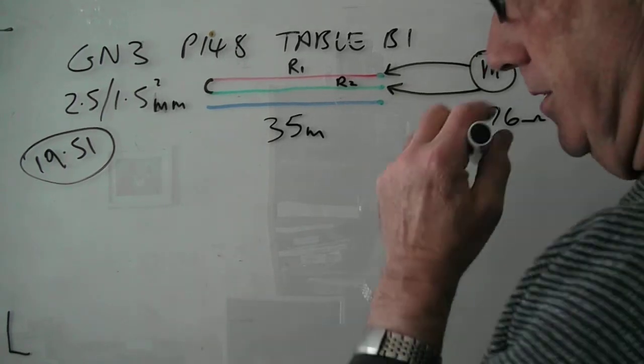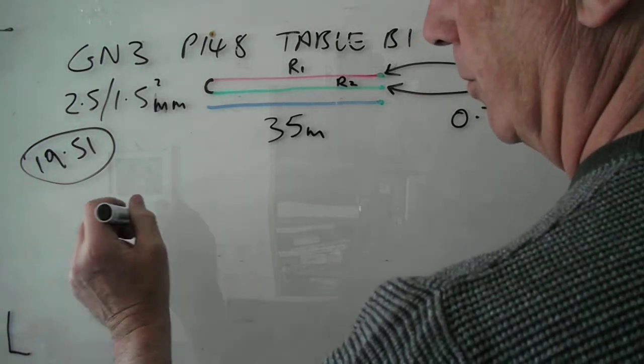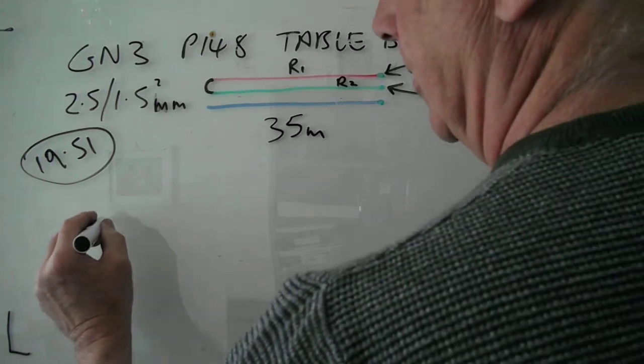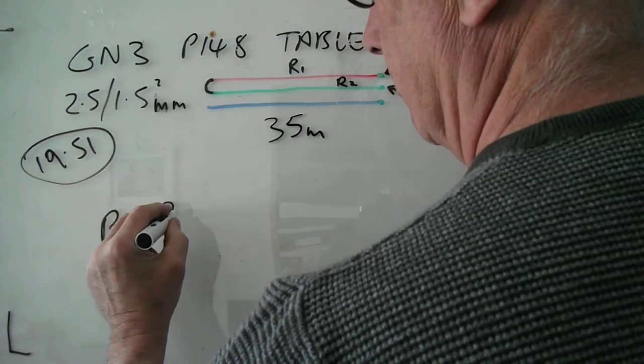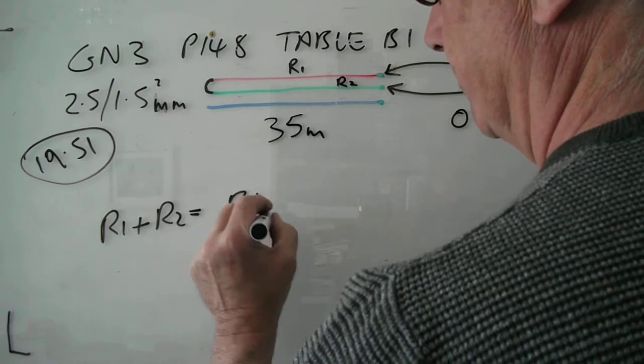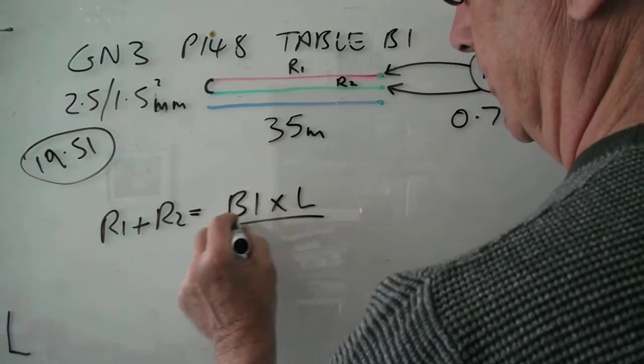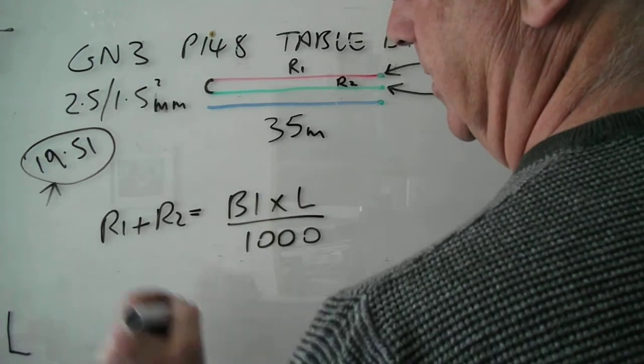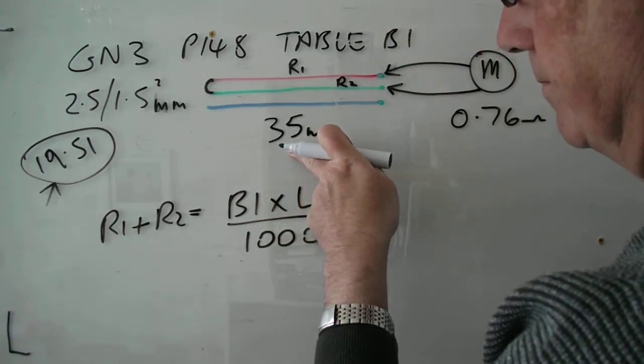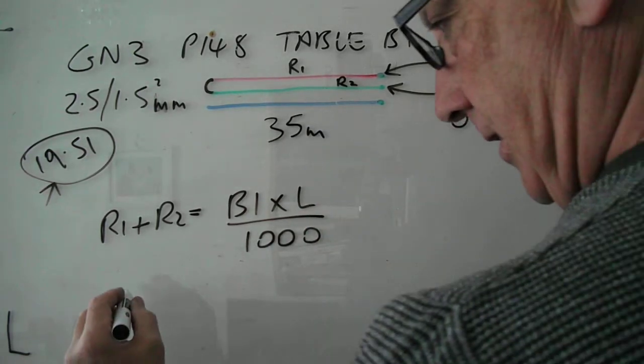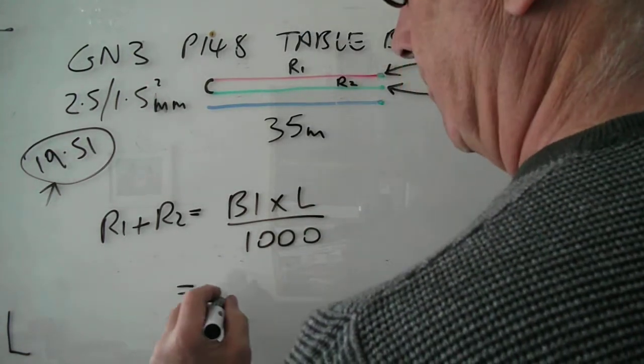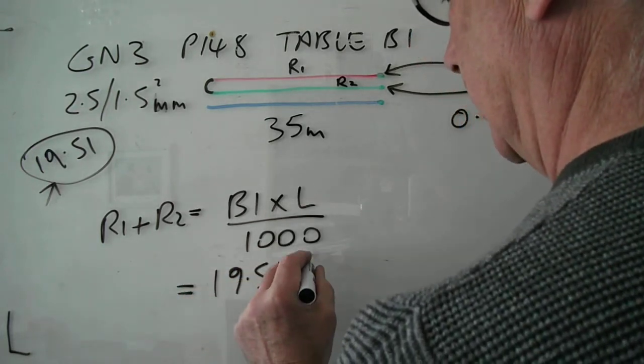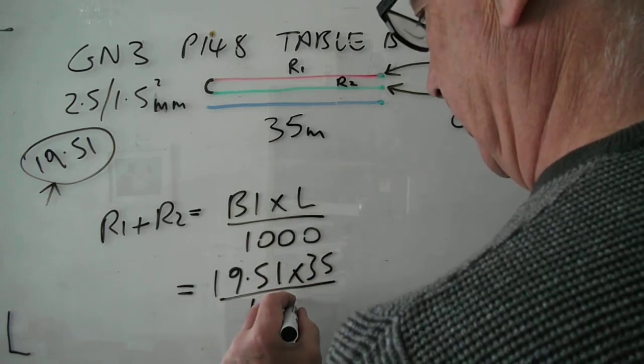So we know the formula is effectively for resistance that cable R1 plus R2 in other words equals B1 times the length divided by 1000. So what we should be getting is 19.51 times 35 divided by 1000.